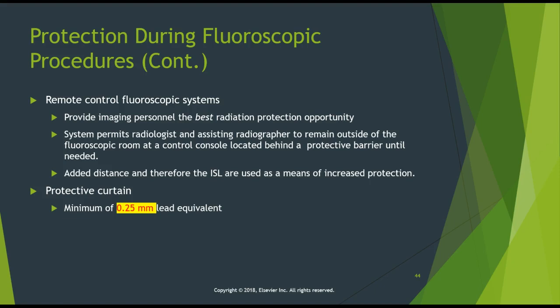However, the protective curtain on the fluoro machine needs to be utilized at all times with the exception of invasive procedures that utilize needles. In that case, the curtain can hit that needle and cause further harm or increase fluoro time with having to reposition. You never want to do that. So in that case, the curtain would be removed, only at the direction of the radiologist. In all other exams, that protective curtain should be located on that fluoro device, on the image intensifier. It does have a minimum of 0.25 millimeter lead equivalent. Okay, remember that number.